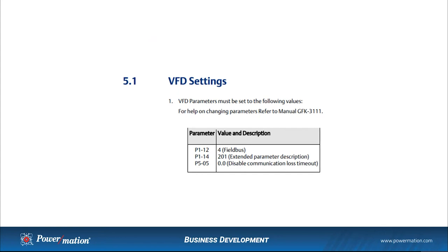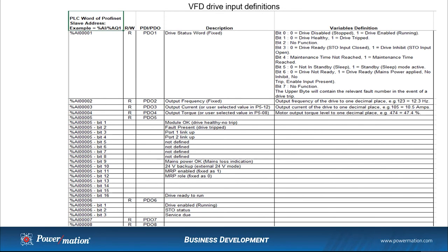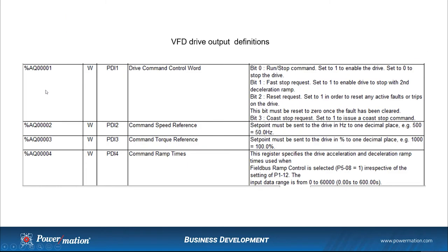The VFD parameters we'll show are the ones needed to set the drive up to communicate over the fieldbus, but there's also software within Machine Edition where you can connect to this drive and go through a full list of parameters. This is just the definition file for the VFD drive — there are eight words of inputs coming in on analog inputs one through eight, bit variable definitions for status and control, and a handful of output words for drive command signals as well as speed reference, torque reference, and ramp times.